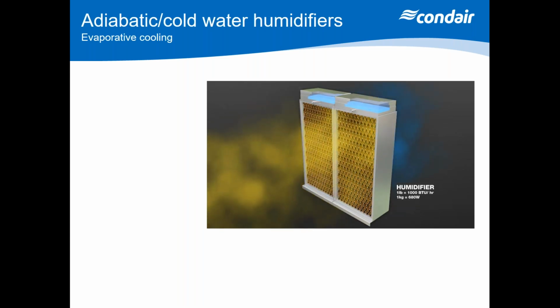Now, normally in an evaporative system, you're going to see glass fibered sheets fixed in a stainless steel cassette. Your air passes through the media, which will have water trickling down through it, and evaporates that water off the media and gives you some humidification and cooling. And what you can see here is that for every 1 litre of water you dissipate out of that unit, you can achieve 680 watts of cooling.